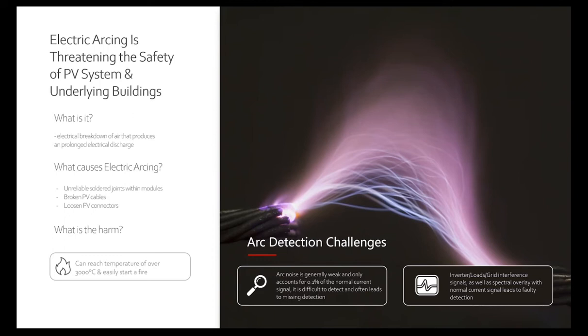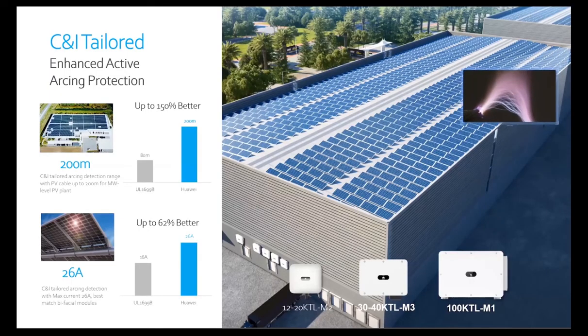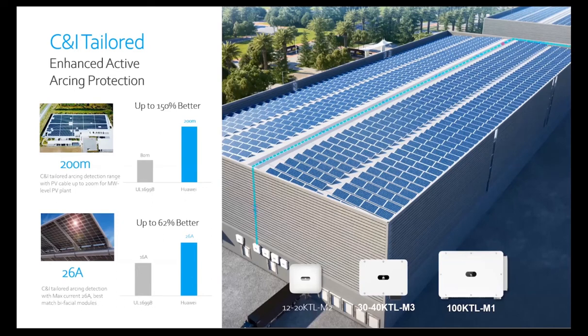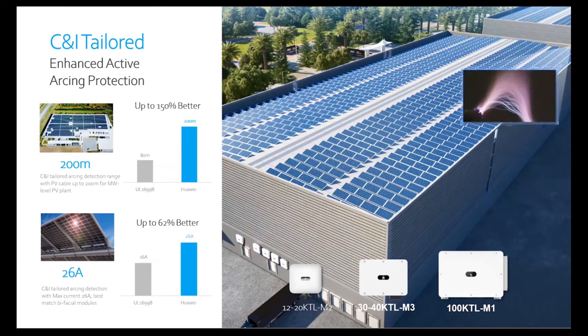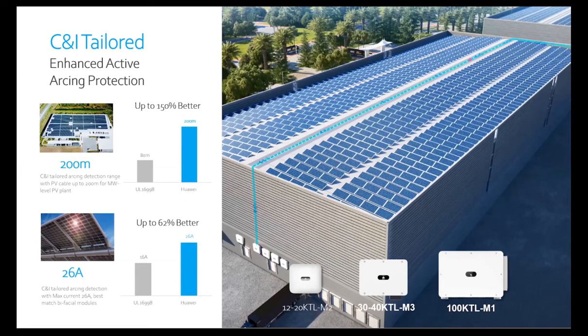So these are all key areas of where this arcing is likely to happen, and these challenges have now been reflected in recent regulations such as the UL 1699B standard. Now, this standard specifically mentions a cable length, and the amount of current that is running through that specific cable. As we all know, these regulations are slightly limited and slightly vague based on the technologies that are becoming available in the industry with the PV modules, and also with the C&I applications, as I explained earlier in the reference cases. The inverters are typically installed in some cases in a plant room, sometimes in a parapet area, or sometimes within the rooftop area itself. So those cable lengths of around 80 meters generally get missed, and if you go well above that length, then the standards are not applicable.